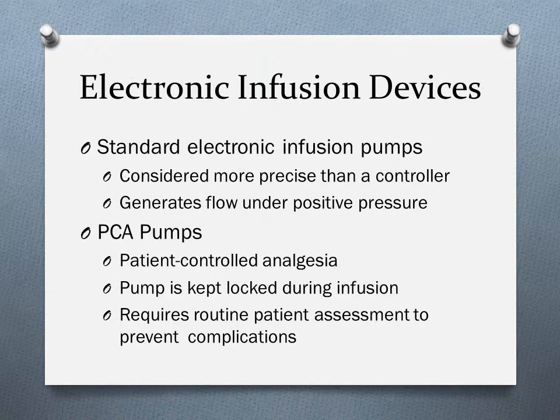Then we have electronic infusion devices, your standard electronic infusion pumps. If resistance develops, the pump will exert additional positive pressure to overcome the resistance, but it will not exceed its preset limit, which is called the occlusion pressure. Most pumps use microprocessor technology.